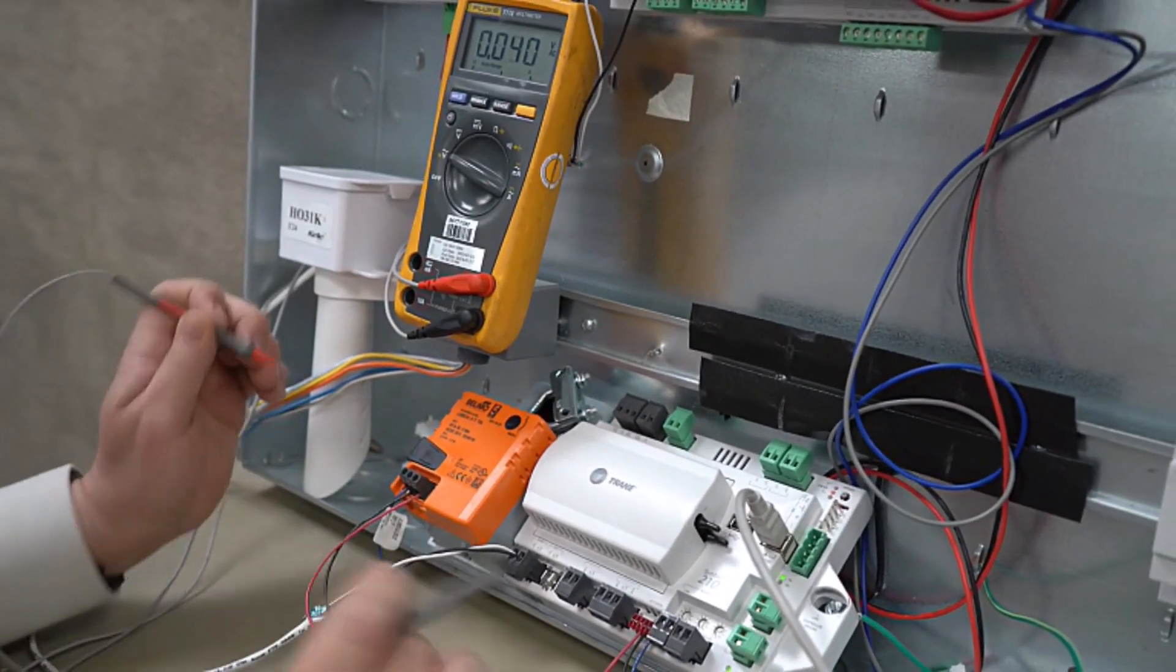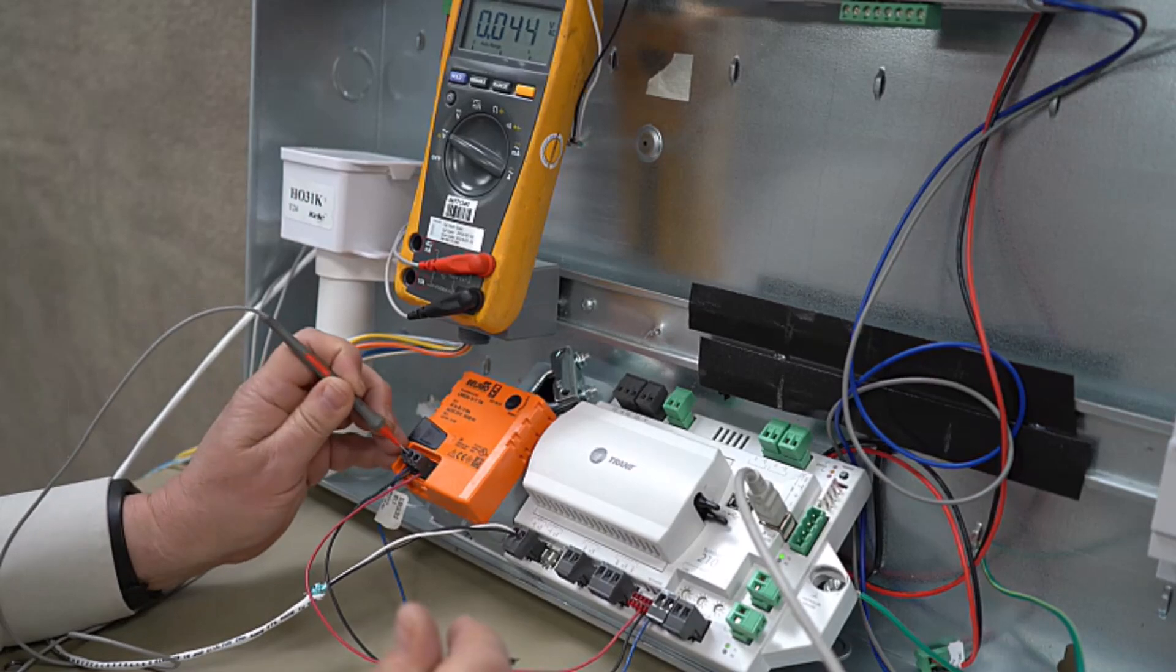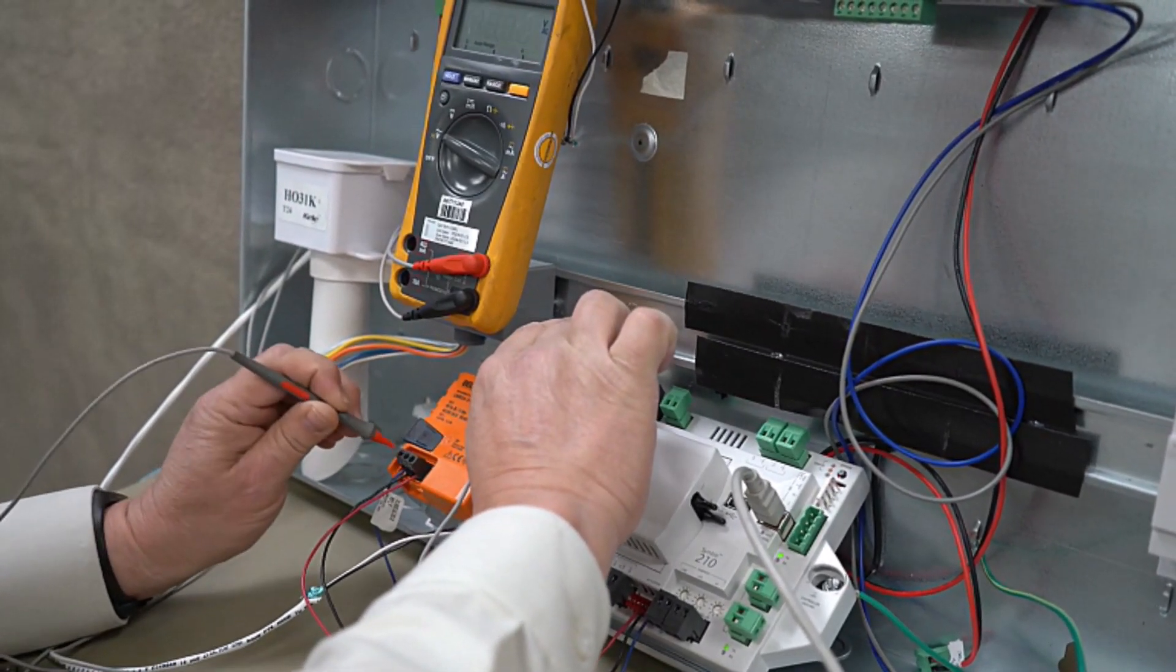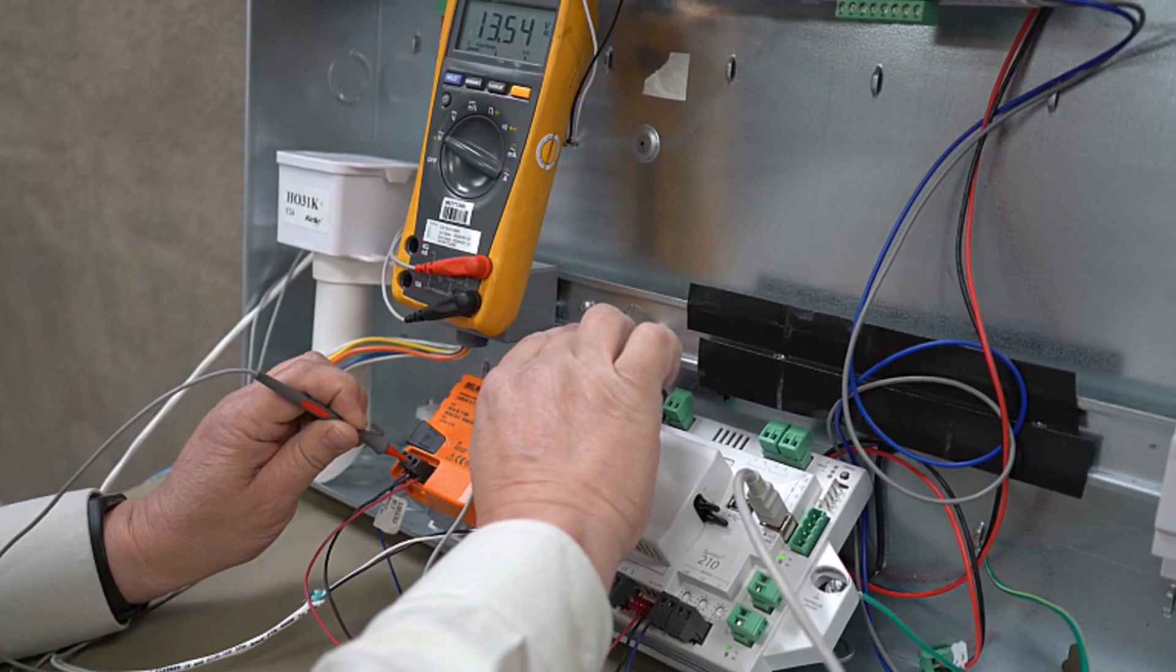This is open right now. We're not actually calling for it to drive open or drive closed. So these ones here should be zero. We get a little bit of trace voltage off there just the way our triacs are wired up and the way they sit.